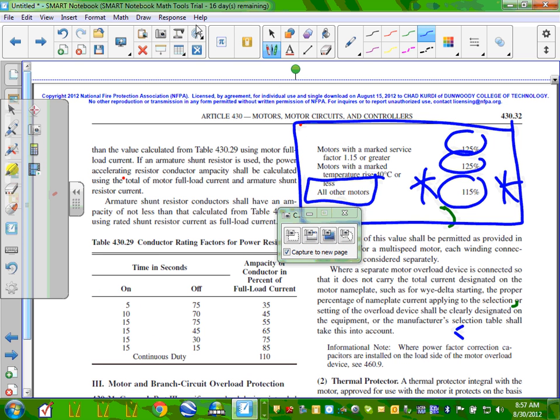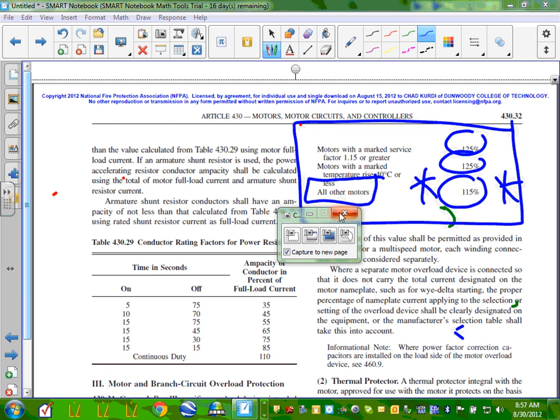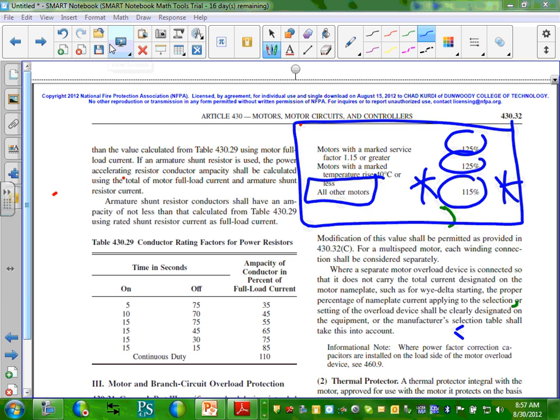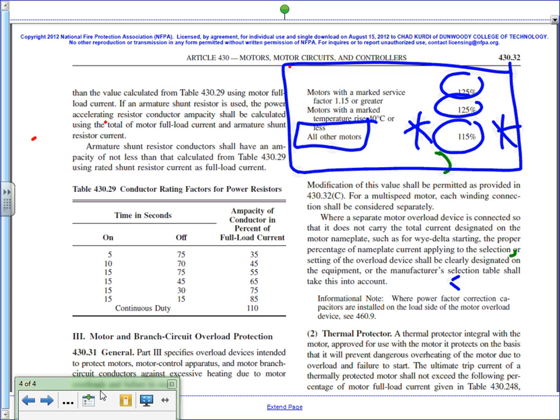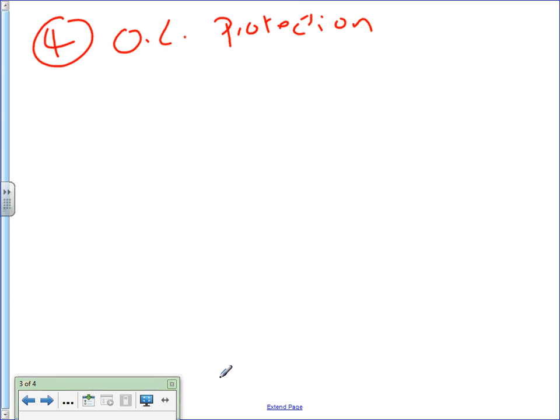Let's go back. And I hope you guys appreciate what we're doing. I like to go to the code first, and then we can, okay, for load. All right, so here's where we were. Okay, so 1.15, everybody knows that was from 430.32. All right, so 1.15 times. This is the only place in the NEC code book that you don't use the full load current, the 17. You use the nameplate. So I have to give you the nameplate now, okay?